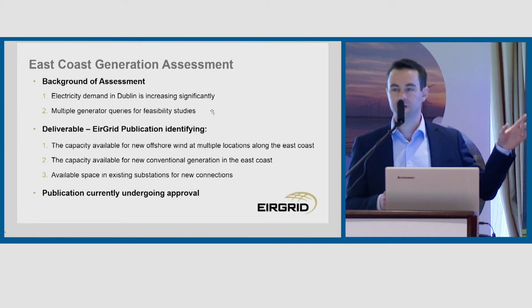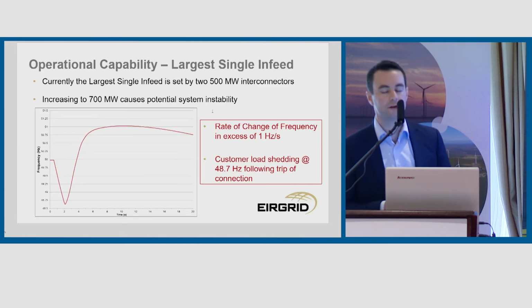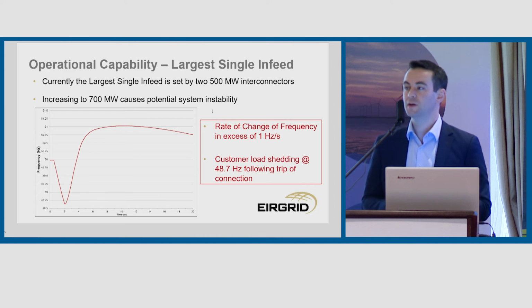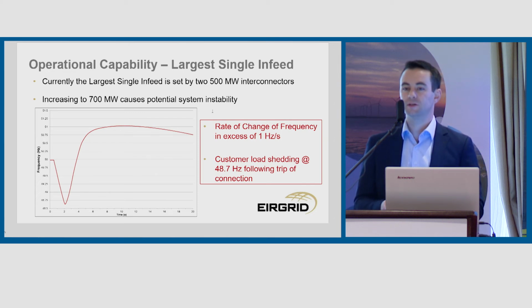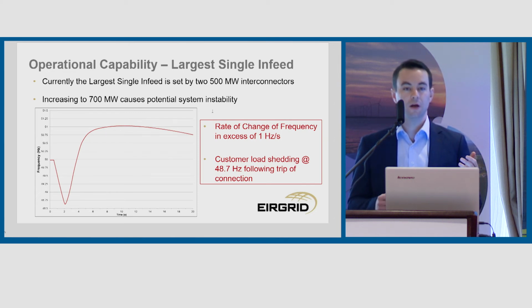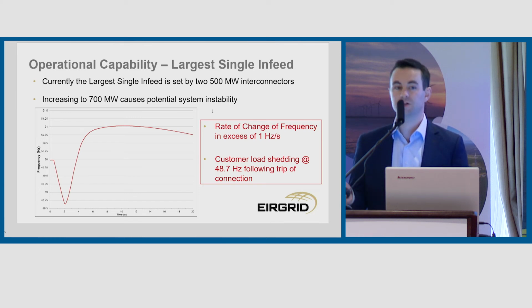As I mentioned, we currently operate the system with a largest single in-feed of 500 megawatts. A lot of our operational practices are set up in order to essentially save the system if we were to lose that connection. So if an interconnector were to trip, for example, we have defined operating reserve products and services that will mean we won't be in a blackout situation or a customer load shedding situation.